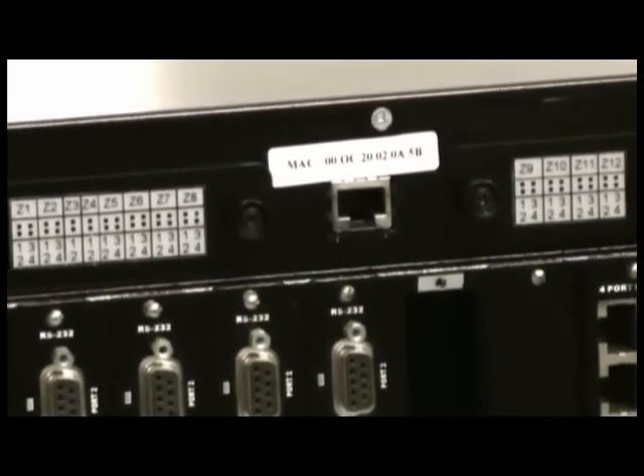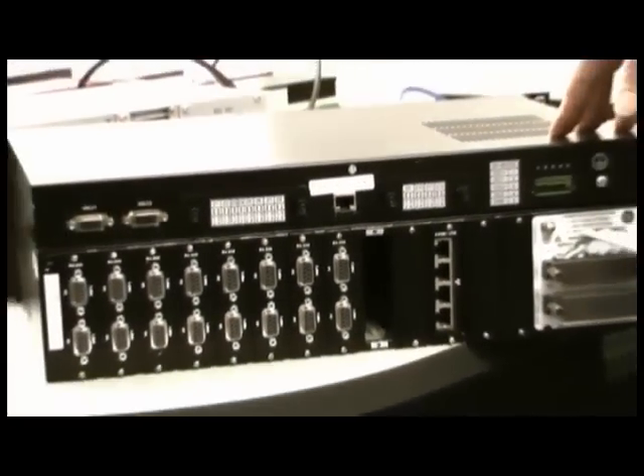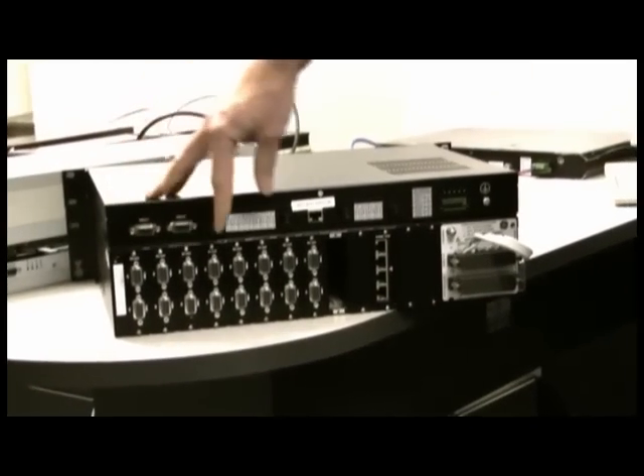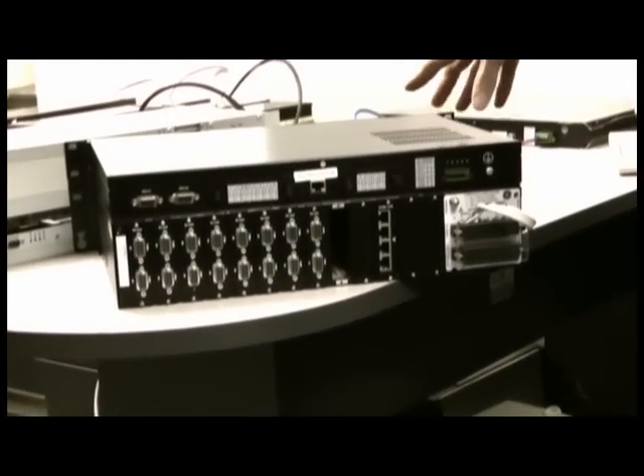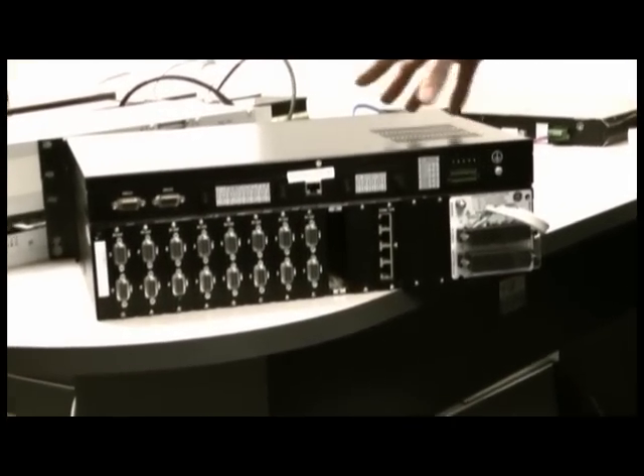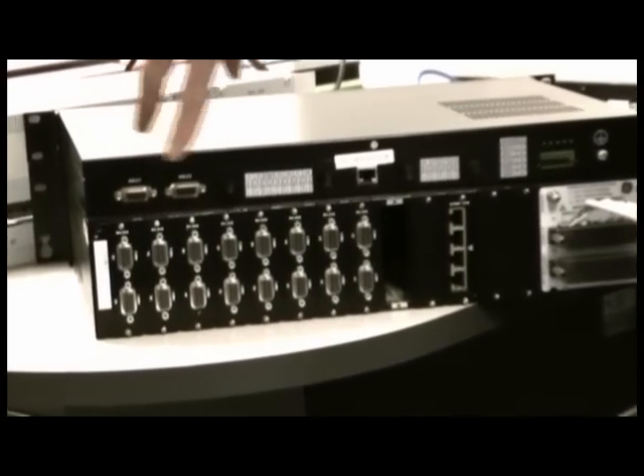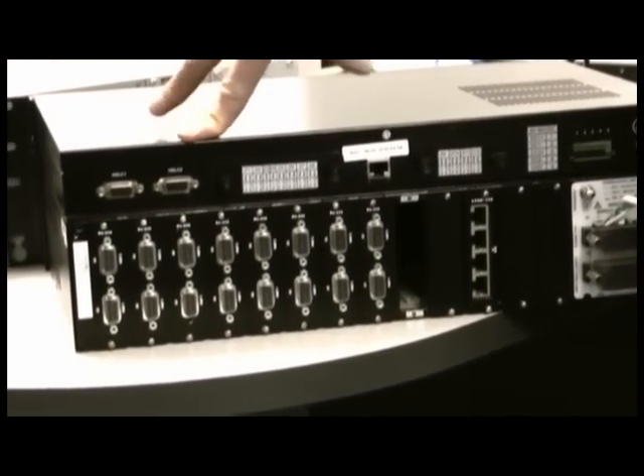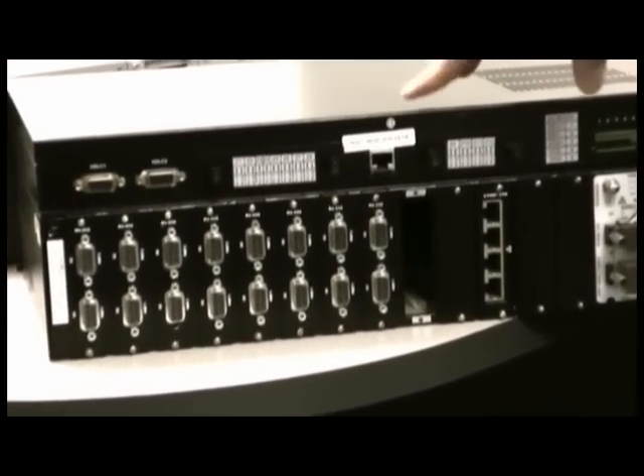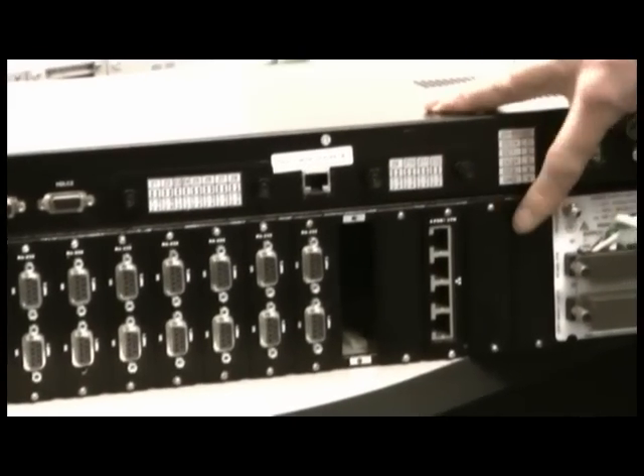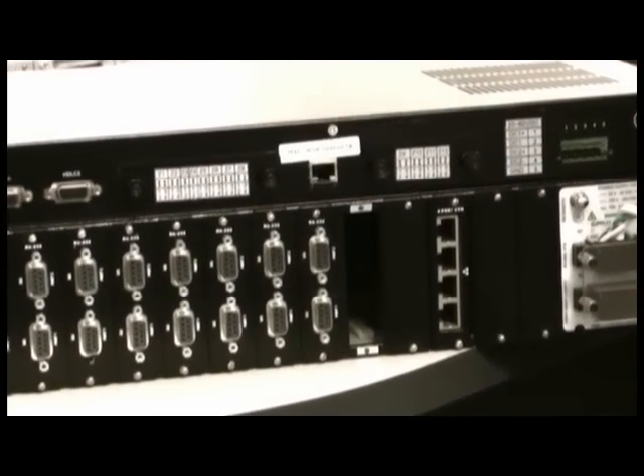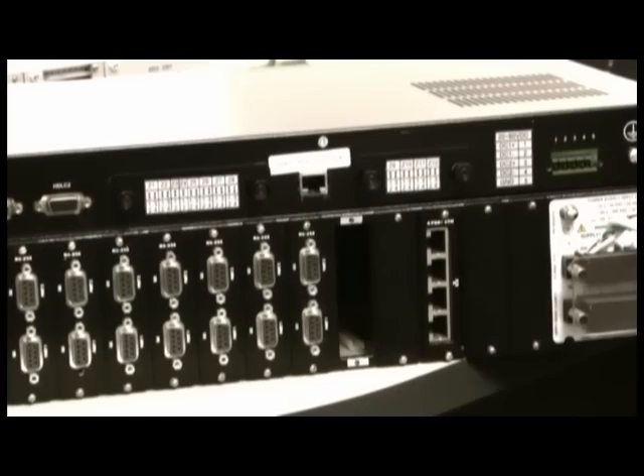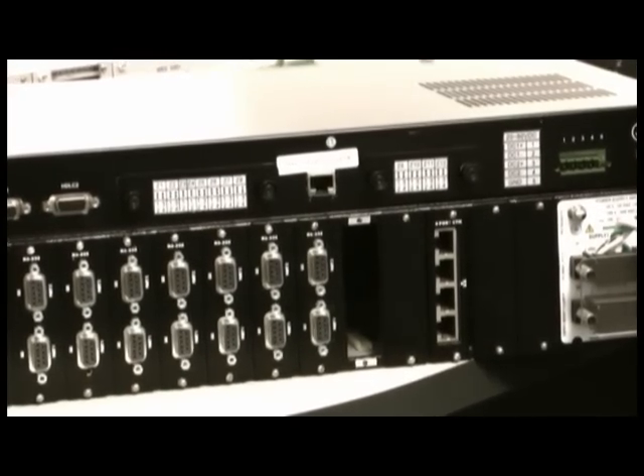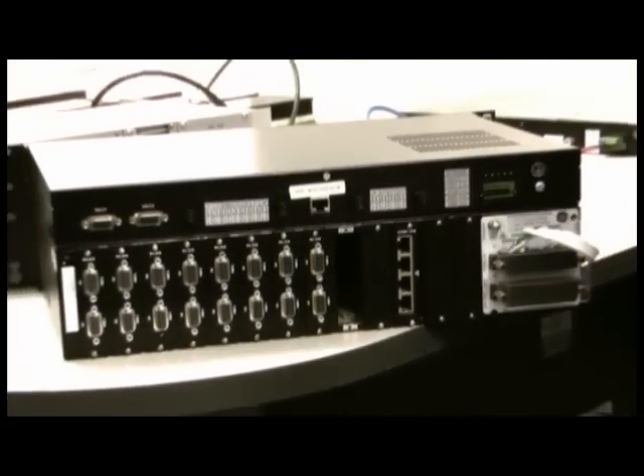So as far as physical connection goes, we hook up power, we replace the serial ports onto the first 7 serial ports on the D400, we move the HDLC cables from the D20 to the 2 HDLC ports on the converter, and then we connect the converter to the D400 using an Ethernet cable between this port here and one of the Ethernet ports on the D400. And that is it as far as physical installation goes. It's that simple.